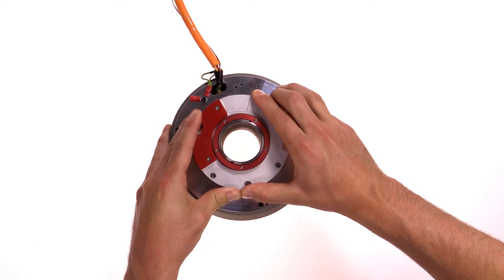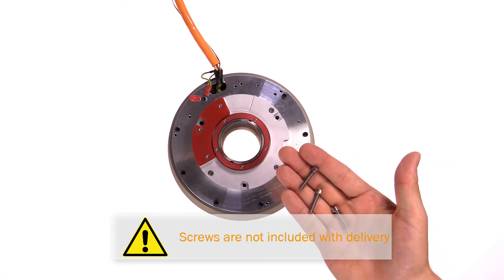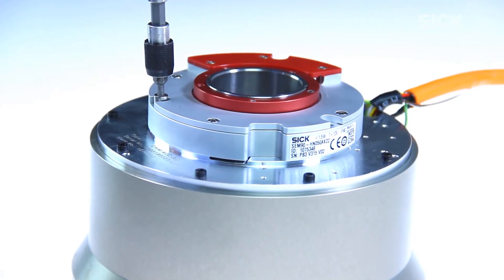Subsequently, the housing is turned until a click confirms that the device snapped completely into the centering collar. To fix the housing, three cylinder head bolts with a minimum breaking strength of 8.8 are needed.